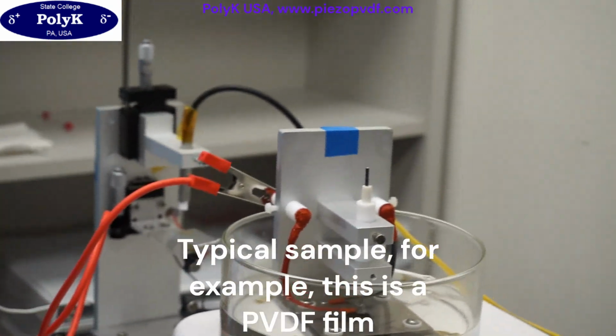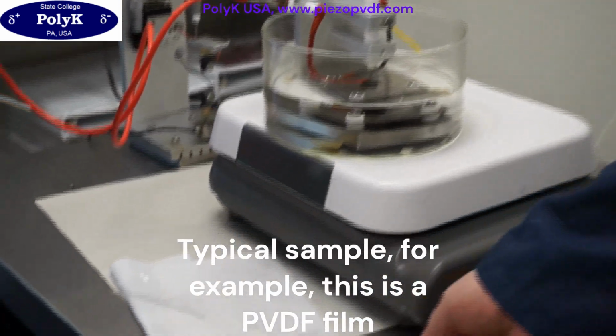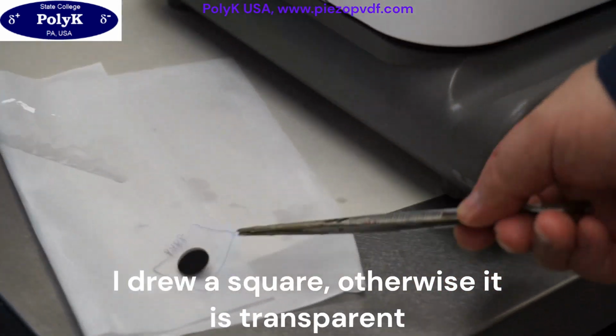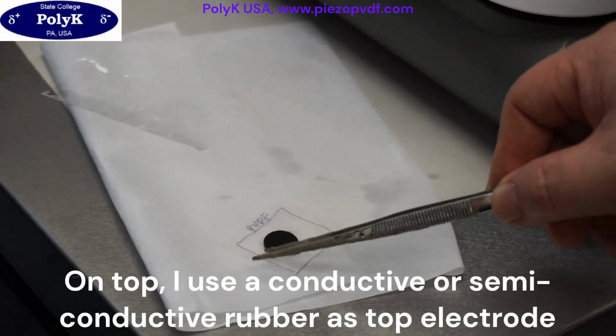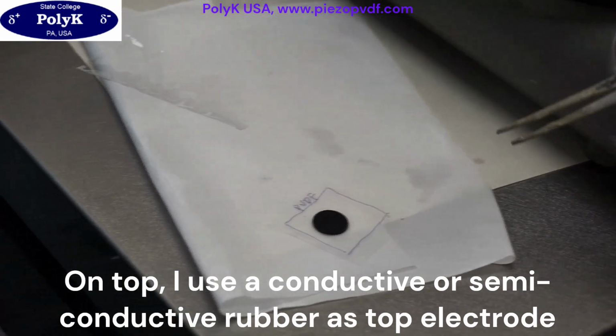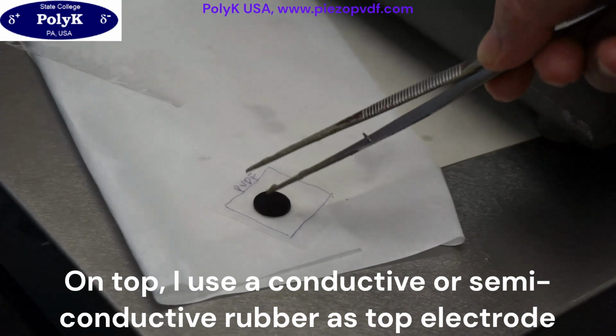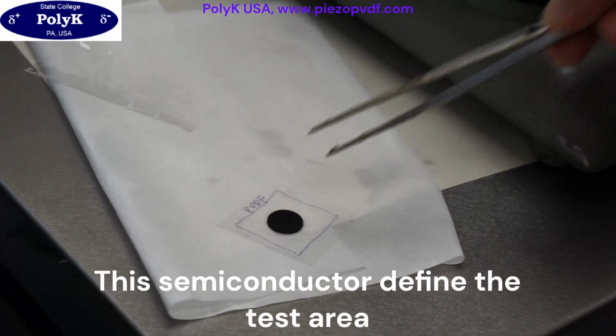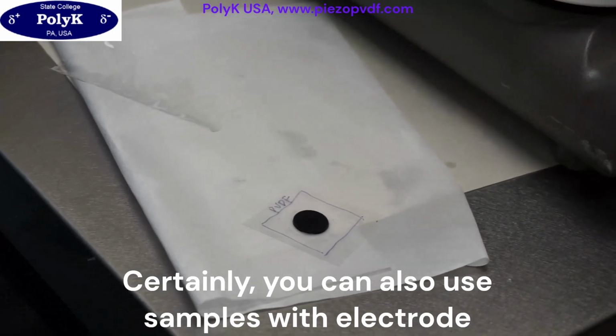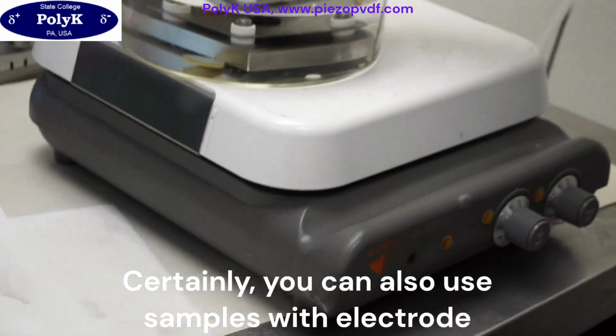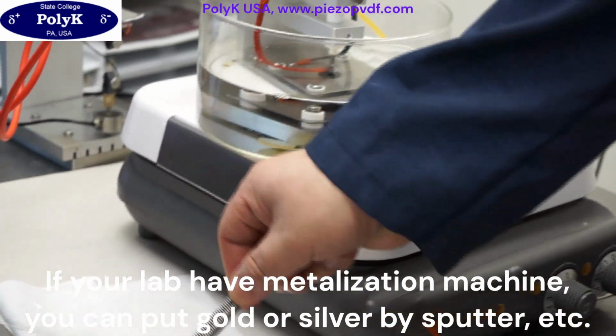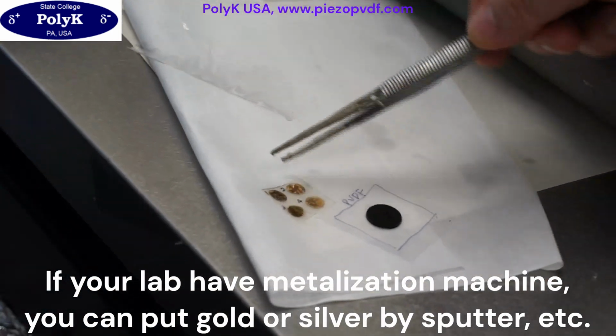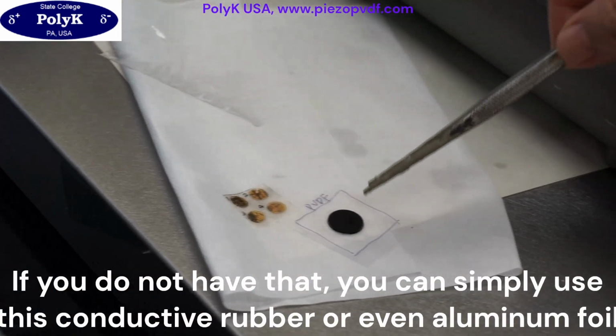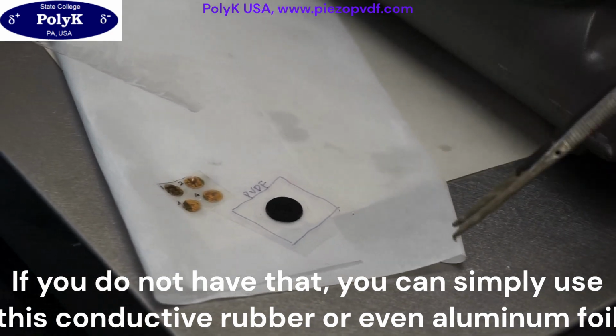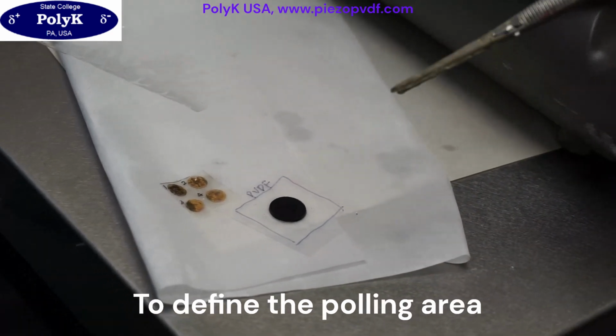A typical sample over here, for example, is a PVDF film. I drew a square so you can see it, otherwise it's transparent. On top, I use a conductive or semi-conductive silicone rubber as a top electrode. This silicone rubber defines the test area. And certainly you can also use a sample with electrodes. If your lab has a metallization machine, you can put on gold or silver by sputtering. If you do not have that, you can simply use a conductive rubber or even aluminum foil to define the poling area. So the power supply is very easy to use.